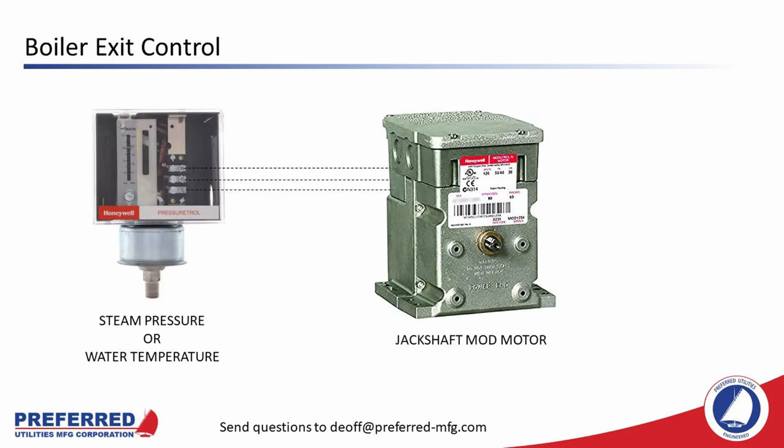In the very smallest boilers, this system gets simplified to two components: a Honeywell L91 direct-sensing steam pressure or hot water sensor/controller and a mod motor that turns a jackshaft. Usually there is an auto-manual switch and a potentiometer for manual control of the firing rate. Back in what I'd call the middle Bronze Age of my career, you'd see these controls on boilers as large as 500 to 600 horsepower. Nowadays, you seldom see this setup on boilers larger than 200 horsepower. Don't know what a jackshaft is? It's coming up in about five slides.